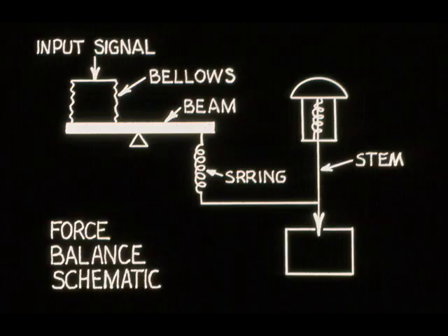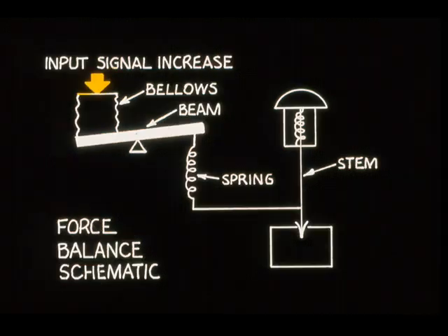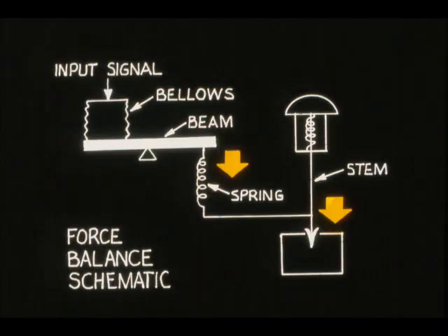In the force balance type, the input pressure is opposed by a spring. The spring tension is changed by the valve stem movement. The design is such that an increase in input signal causes the bellows to force the left-hand end of the beam downward. The valve stem then moves downward, putting more tension on the spring, and this action restores the beam to balance.